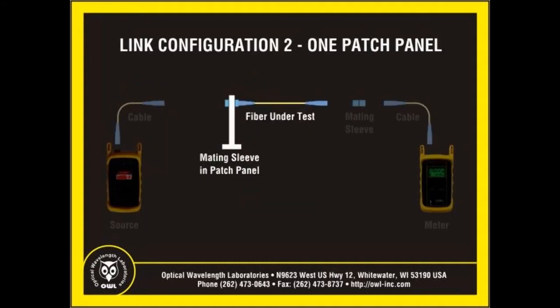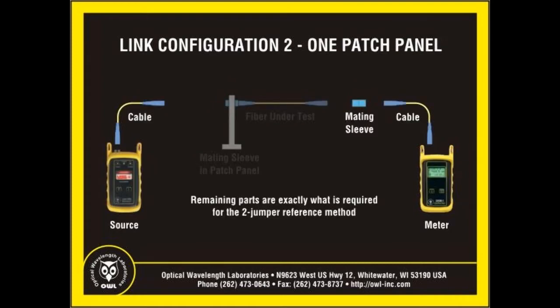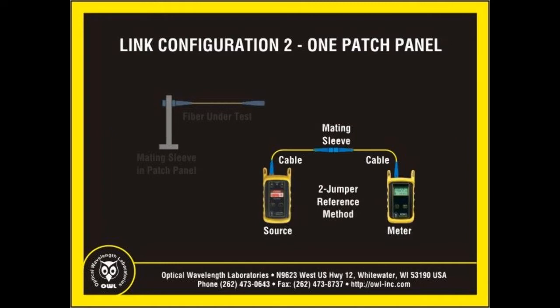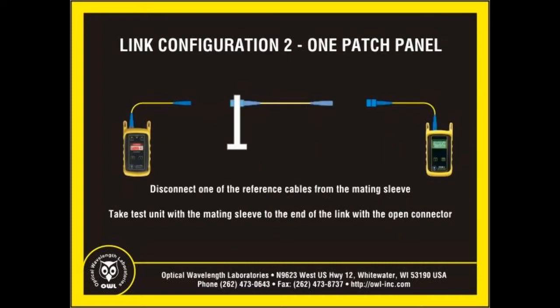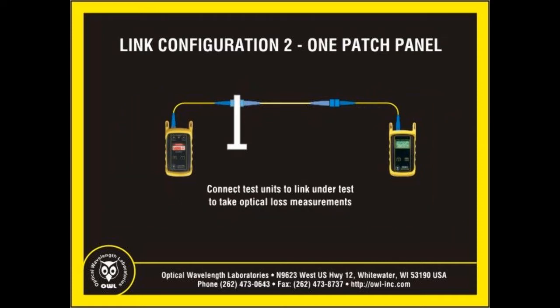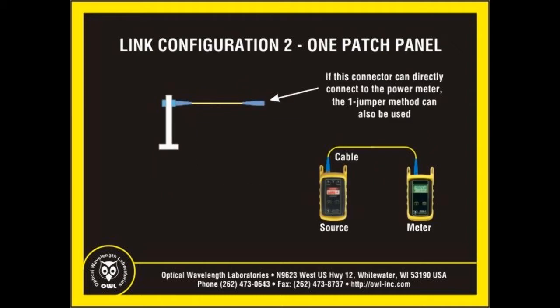The second link configuration has a patch panel on one end and an open connector on the other end. What remains from the test configuration is two test cables and a mating sleeve — exactly the pieces needed for the two-jumper method. Simply connect the power meter and light source together with the two test cables and mating sleeve to set the reference. Once the reference has been set, disconnect one of the test cables from the mating sleeve — it doesn't matter which one, as long as you leave both cables attached to their respective test units. Insert the link under test between the single cable and the mating sleeve to take measurements. Note that the one-jumper method can also be used here if the open connector on the fiber under test can directly plug into the power meter detector port.